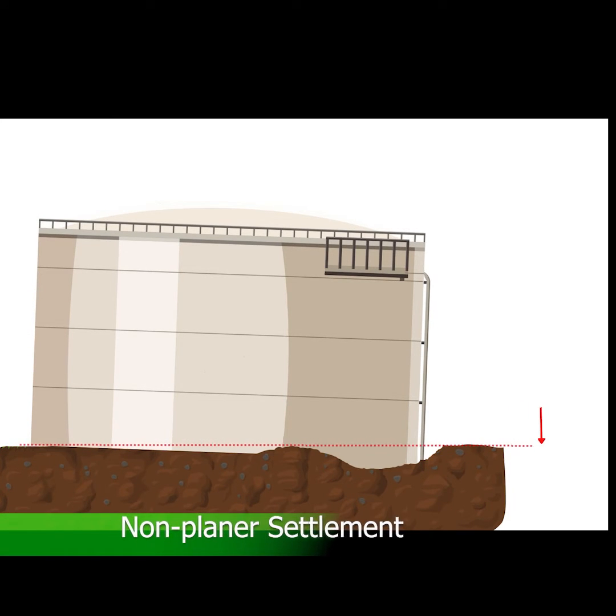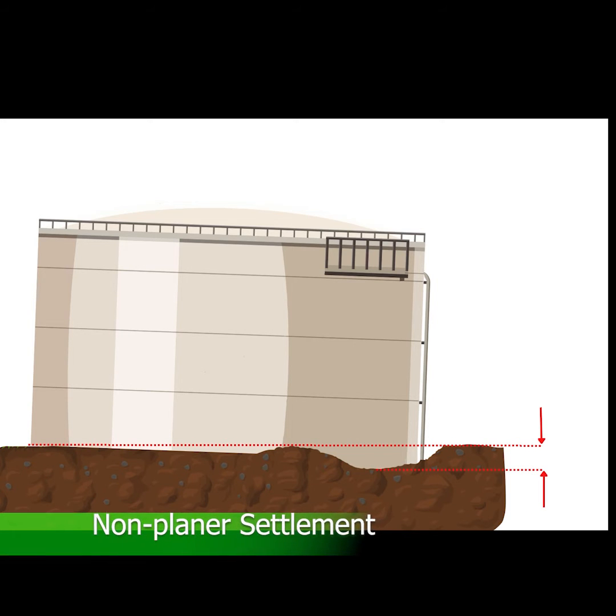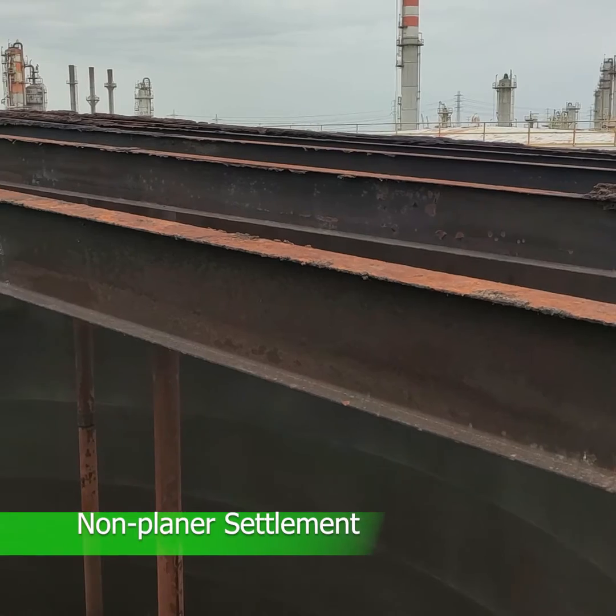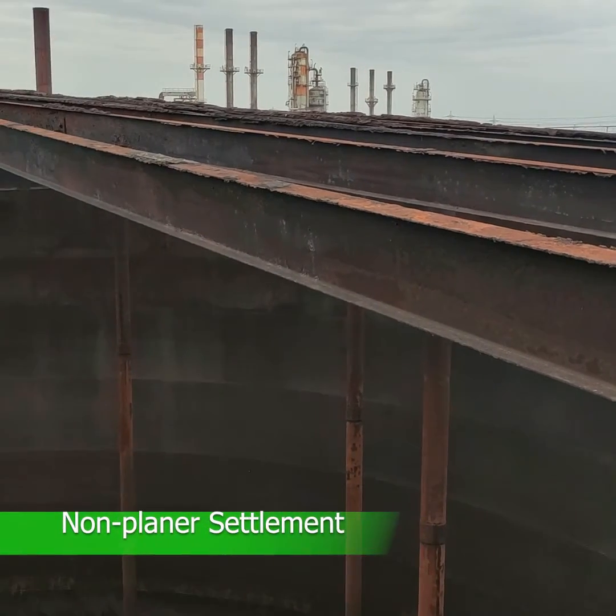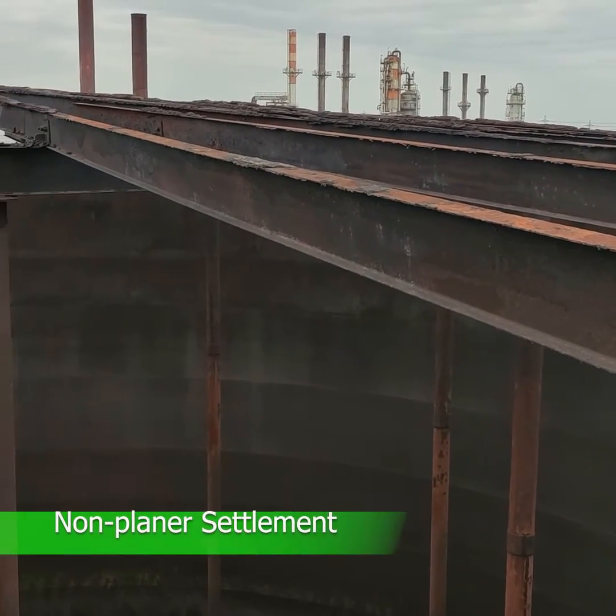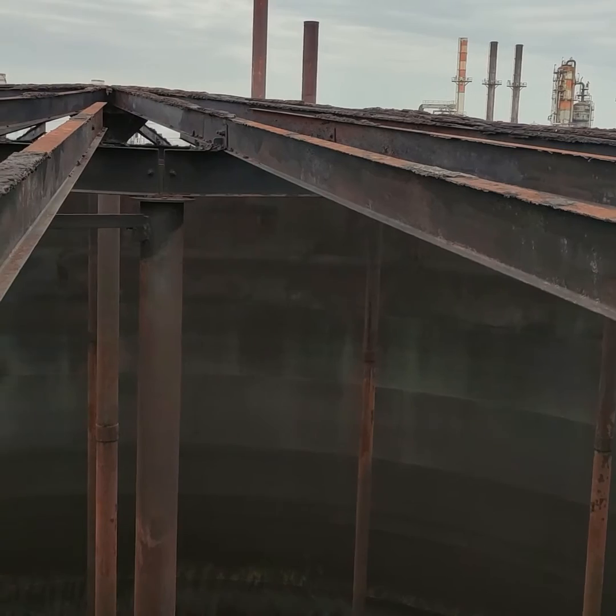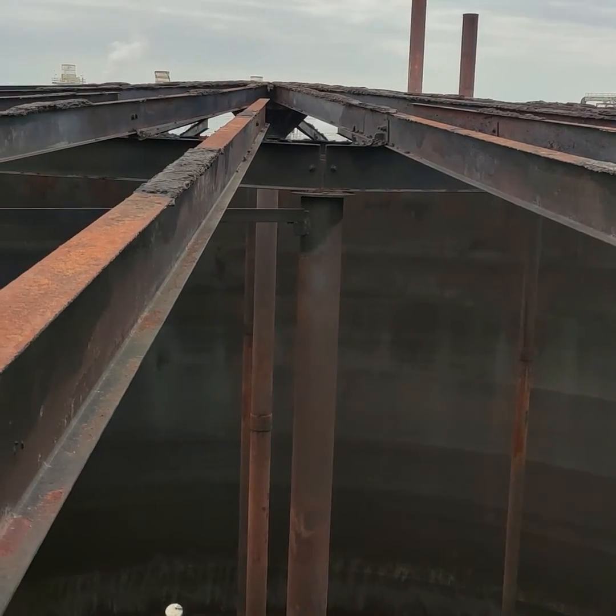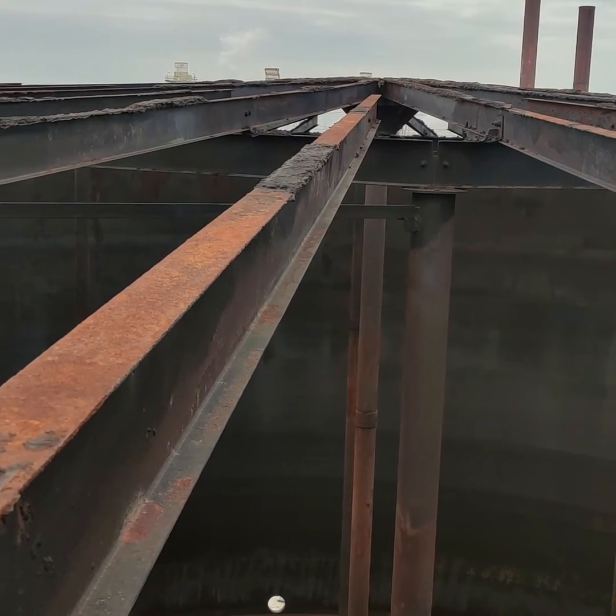Due to the fact that a tank is a rather flexible structure, the tank may settle in a non-planar configuration. This settlement can lead to out-of-roundness at the top of the shell and may also affect the internal roof support structures, such as columns, rafters and girders.